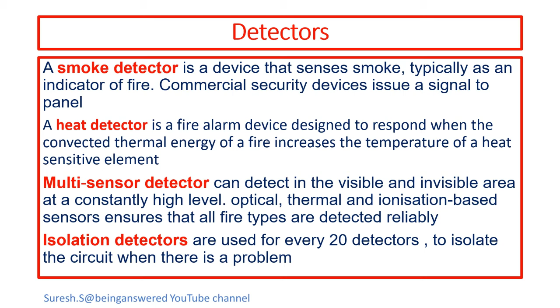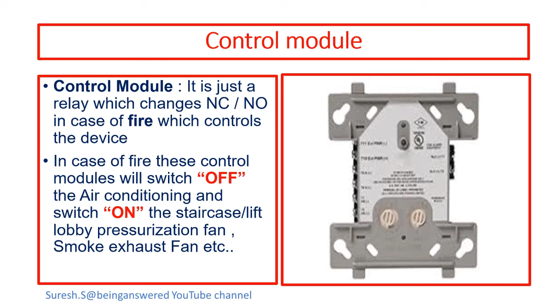Let us see about control module. Control module is just a relay which changes NC to NO in case of fire, which controls the device. In case of fire, these control modules will switch off the air conditioning and switch on the staircase, lift lobby pressurization fan, smoke exhaust fan, etc.